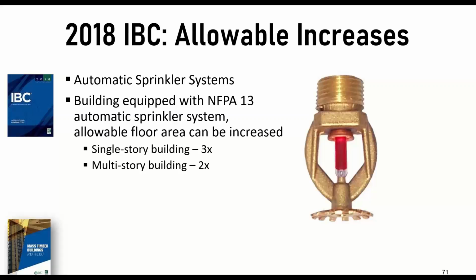So there are some times in the building codes when you get to increase your total square footage permitted for those structures. And that's typically associated with when you have an NFPA 13 or a complete NFPA 13 sprinkler system, pardon me. So you're allowed to increase your allowable floor area up to 3 times if you're a single story building. Again, equivalent risk, equivalent performance. So fighting a fire in a single story building isn't as challenging as it would be in a multi-story building. So you get to increase your allowable floor area 3 times for a single story building, provided it's sprinklered. And the same with a multi-story building. You can increase it 2 times. And the code references this as 300% and 200% increases.